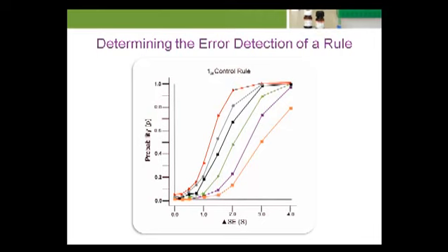In this plot, we're examining the power curve of the 1-3S rule when evaluated multiple times. The bottom curve is for a single evaluation. The top curve is for 20 evaluations. Notice that if the delta SE critical is above 4, the 1-3S rule would likely be suitable.